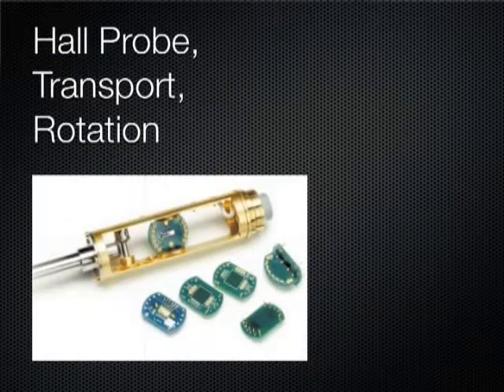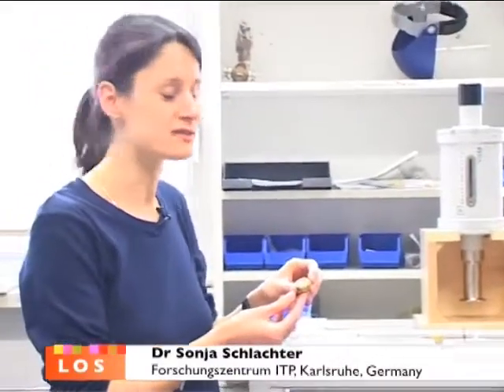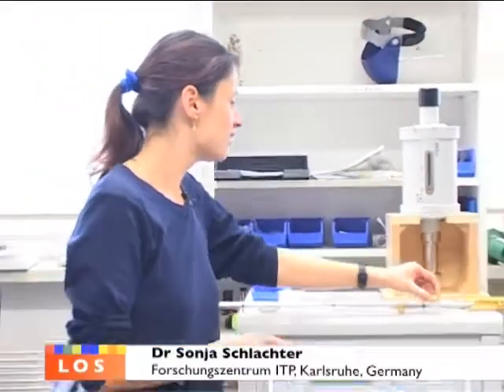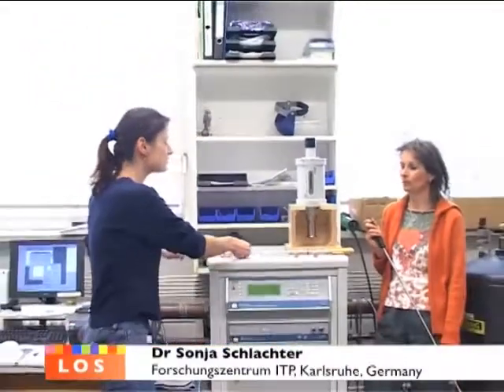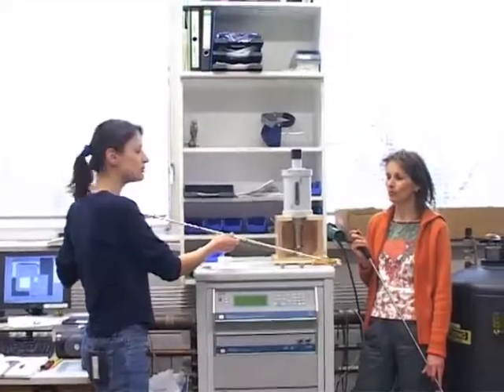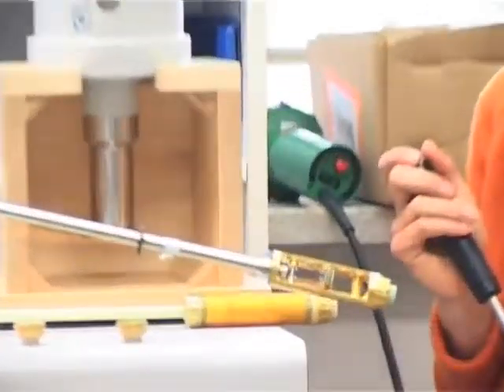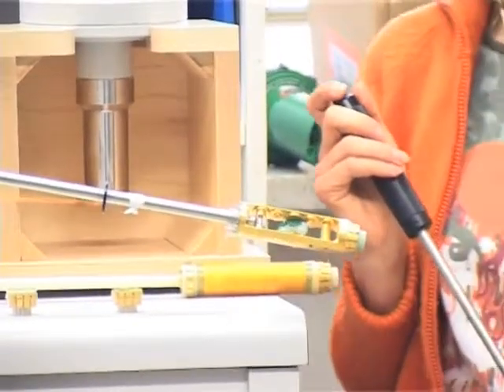With this system, we can make Hall probe measurements, for example, with this sample holder. This is a sample holder to make resistivity measurements. With this sample holder, we can even rotate samples in the cryostat in a magnetic field to measure angular dependencies. The advantage of this PPMS system is that it can be controlled remotely.